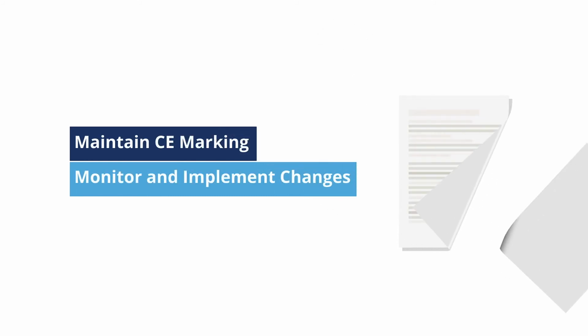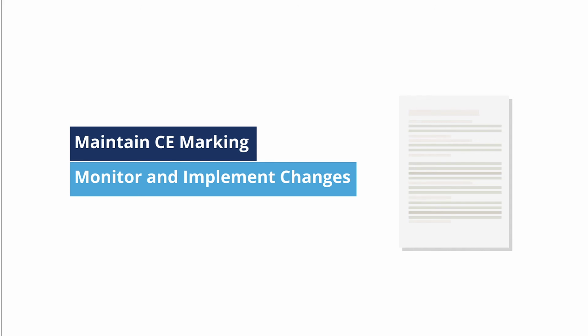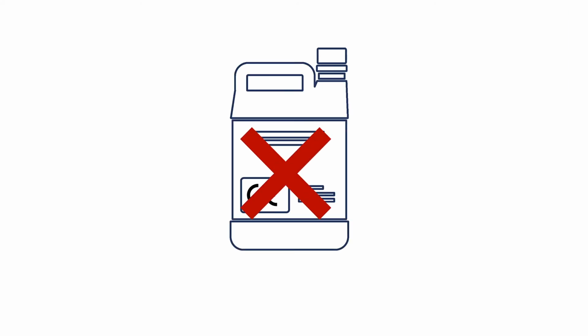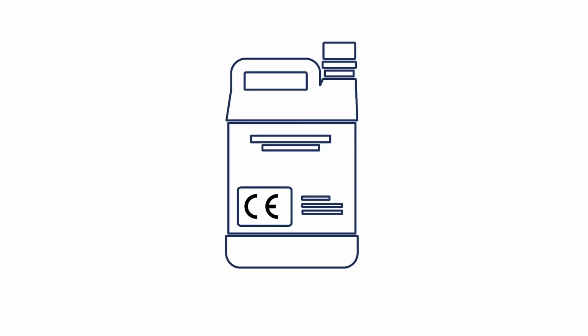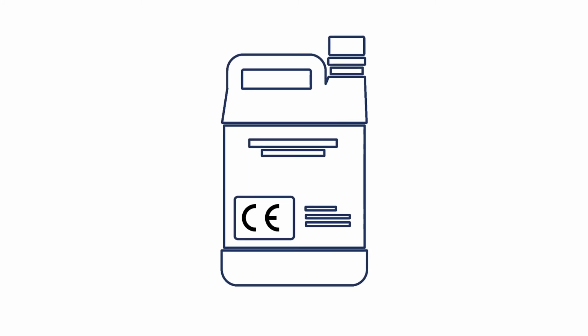Also, in general, CE marking standards change every 5 to 10 years. It's the manufacturer's responsibility to monitor and implement any changes. Once a new standard is implemented, the old standard is no longer valid, and the product has become non-compliant. However, while there may be exceptions, products that were originally in compliance at the time of market entry can still be sold.